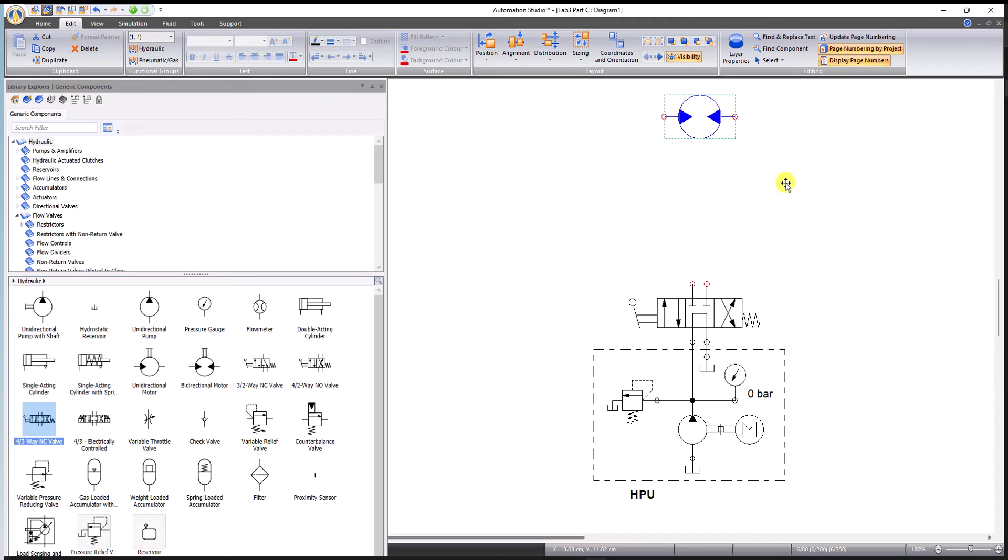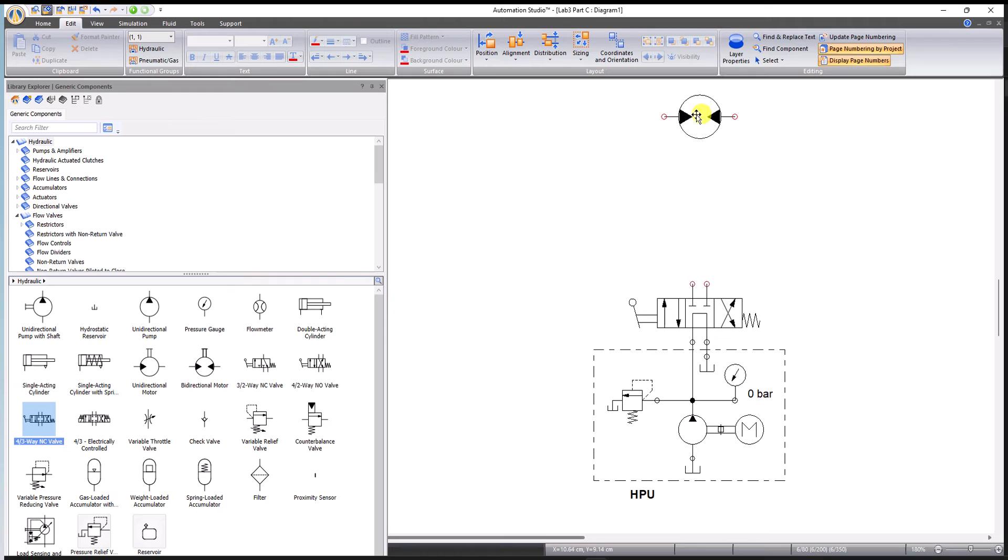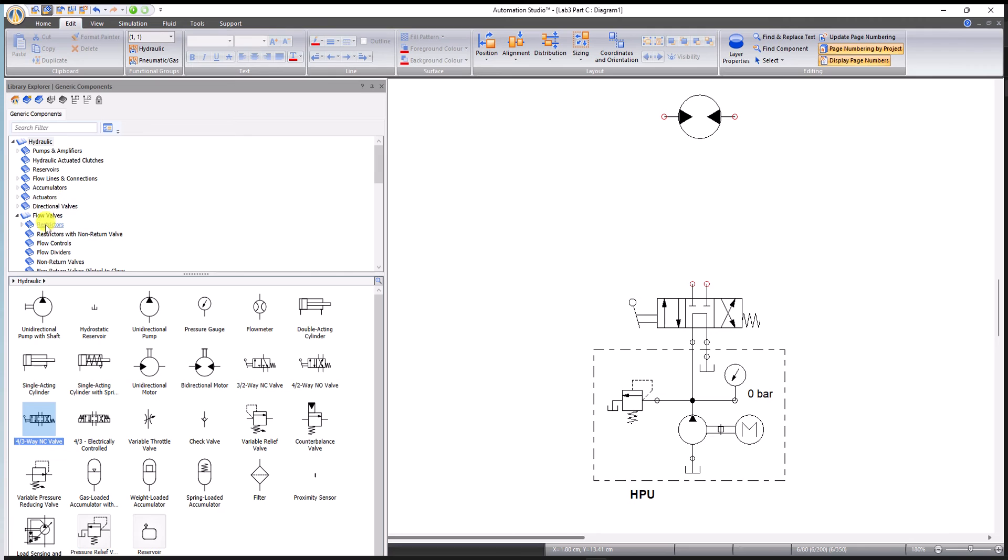This will allow the pump to still run but at low pressure when we close this central block and stop the motor from spinning. Now the motor needs some speed control. We need a unidirectional flow control valve that will only affect the motor speed in a clockwise direction.